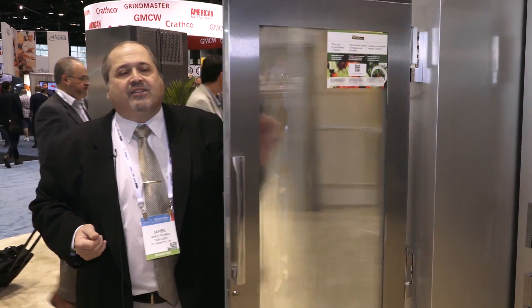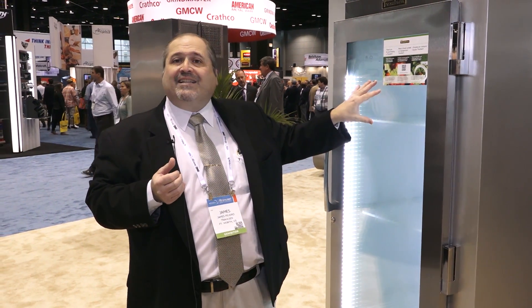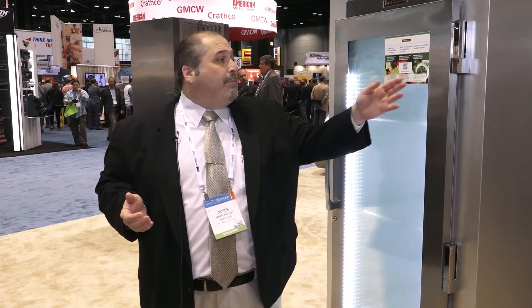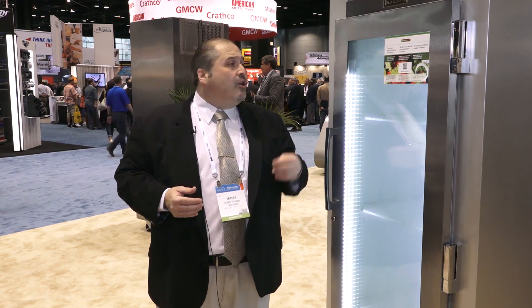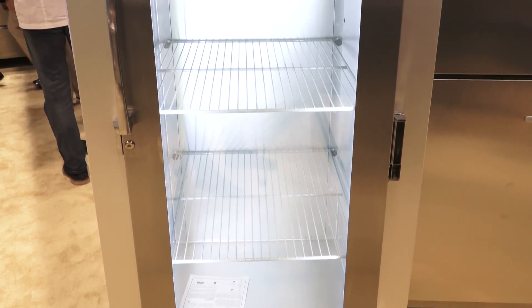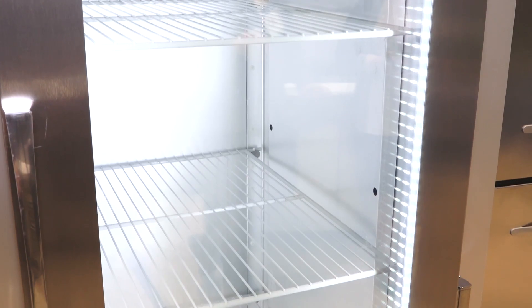The other thing that design does is it saves the BTUs, or the heat generated from those lights, from being placed inside the cabinet where they would have to be refrigerated, hence using energy. By putting them in the doors, those BTUs are instead transferred into the glass itself and used to clear the glass of any fog or moisture. So it eliminates the need for energy-consuming door perimeter heaters, saving energy while clearing the door of any fog after the door has been opened.